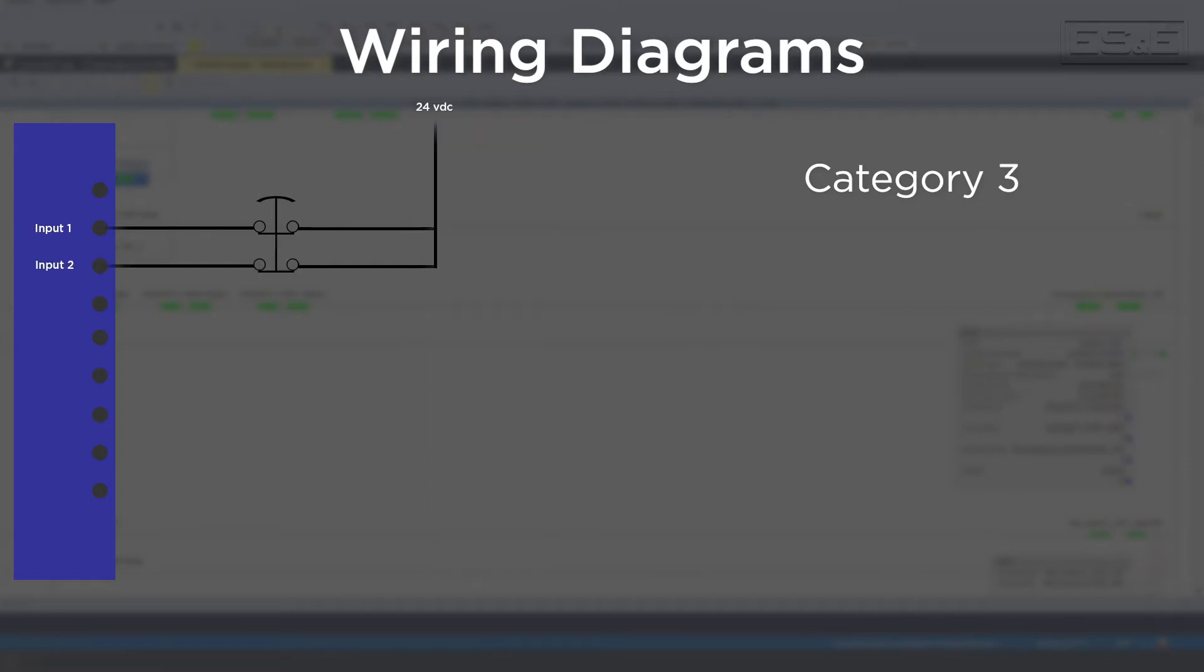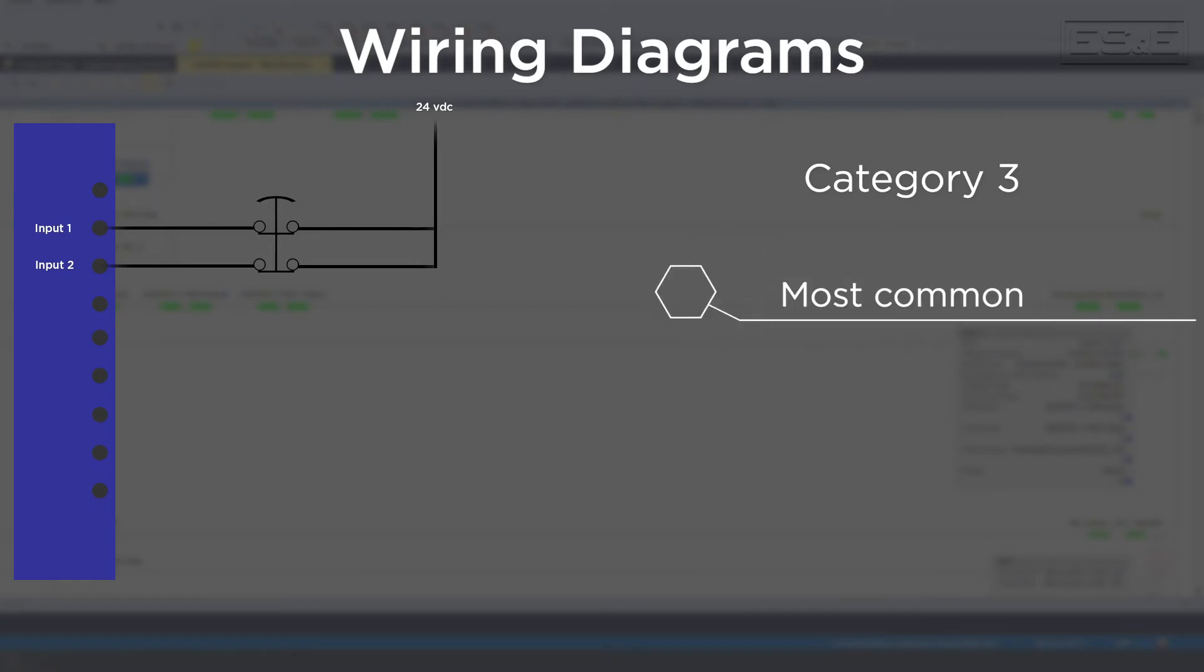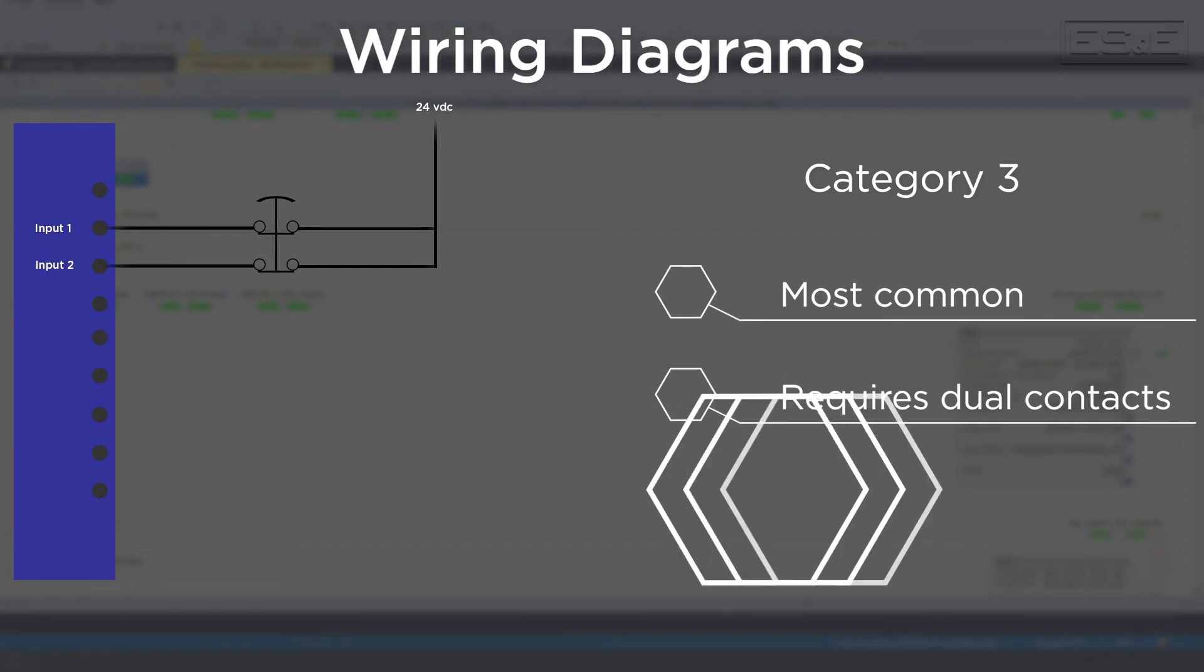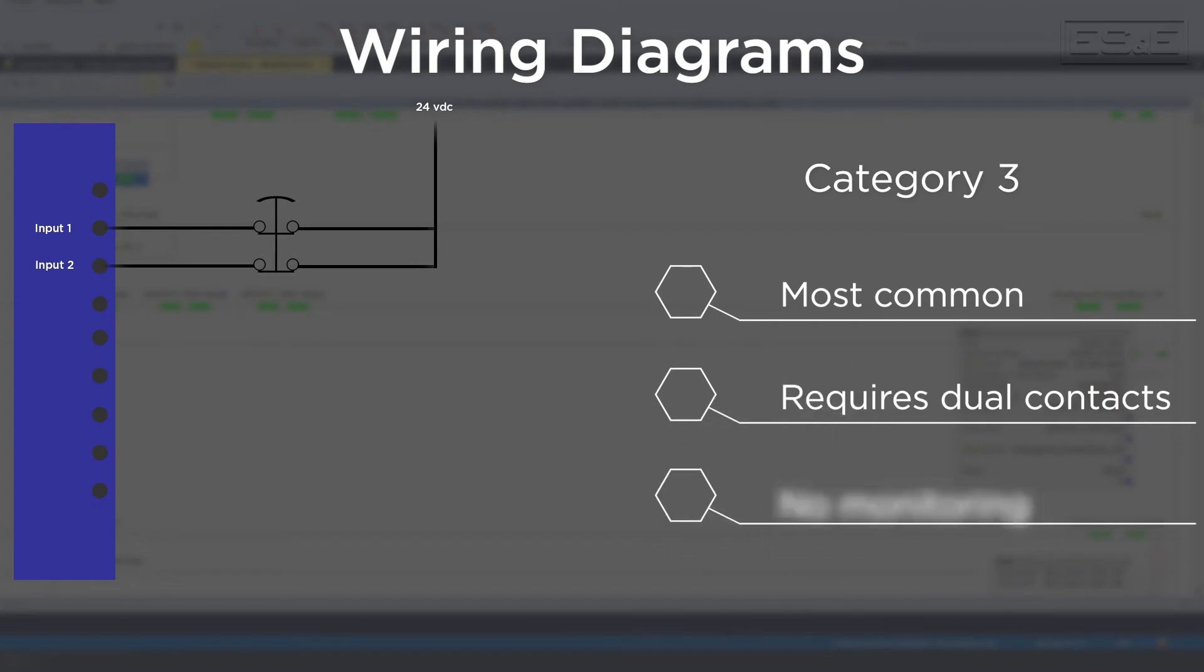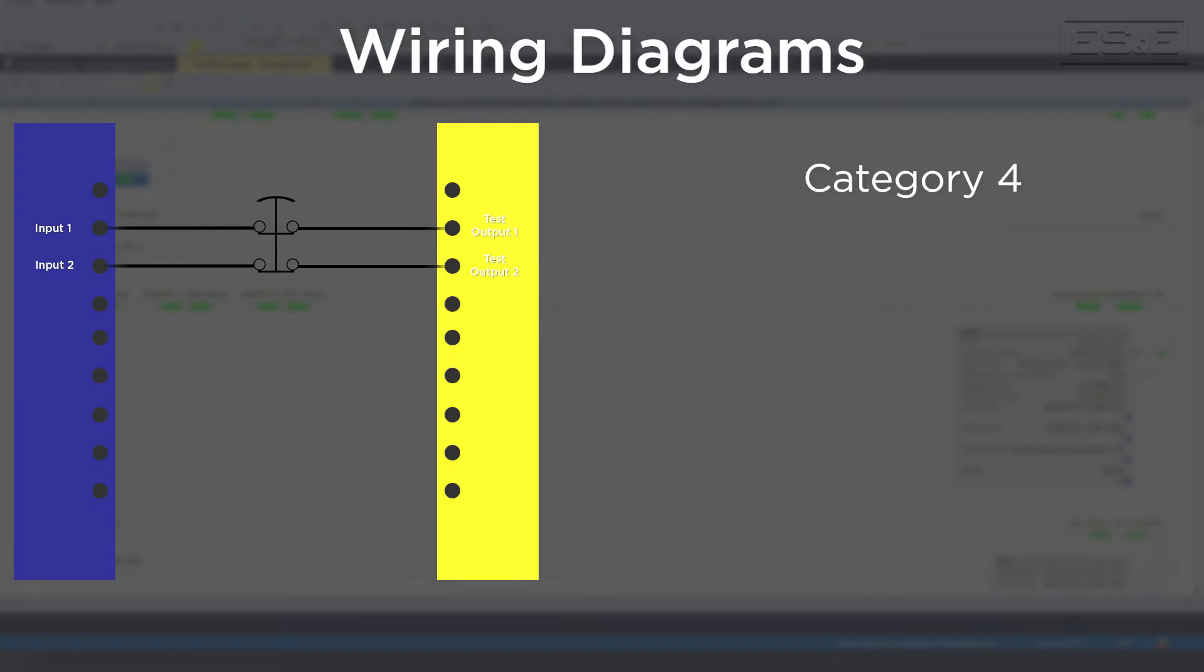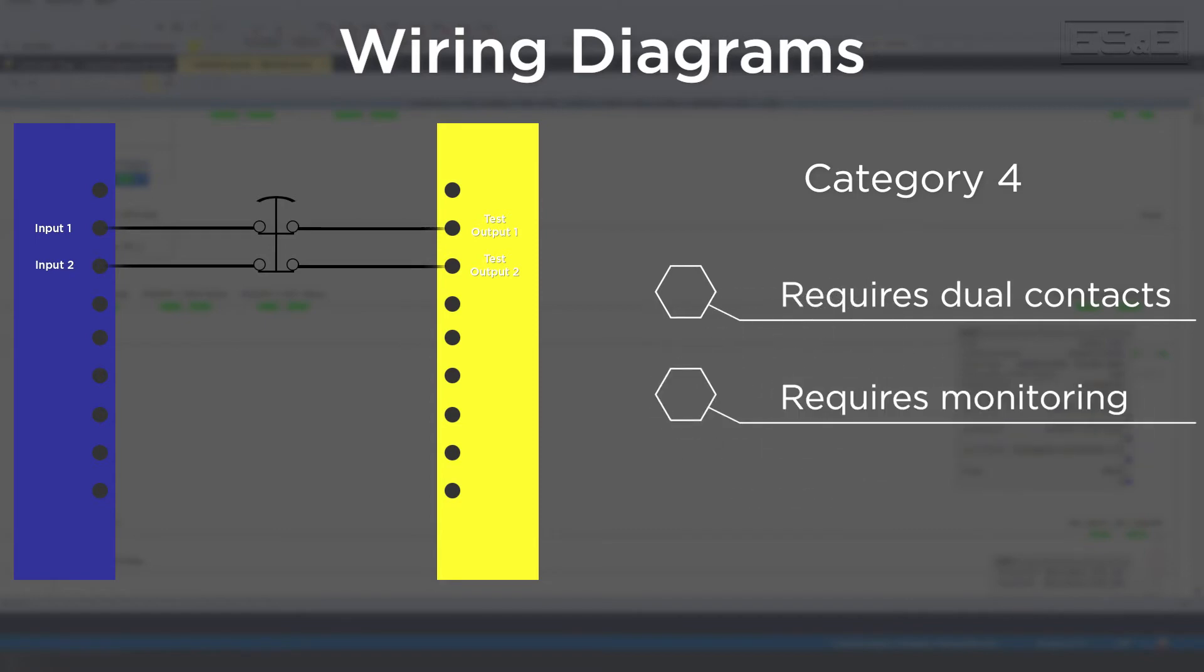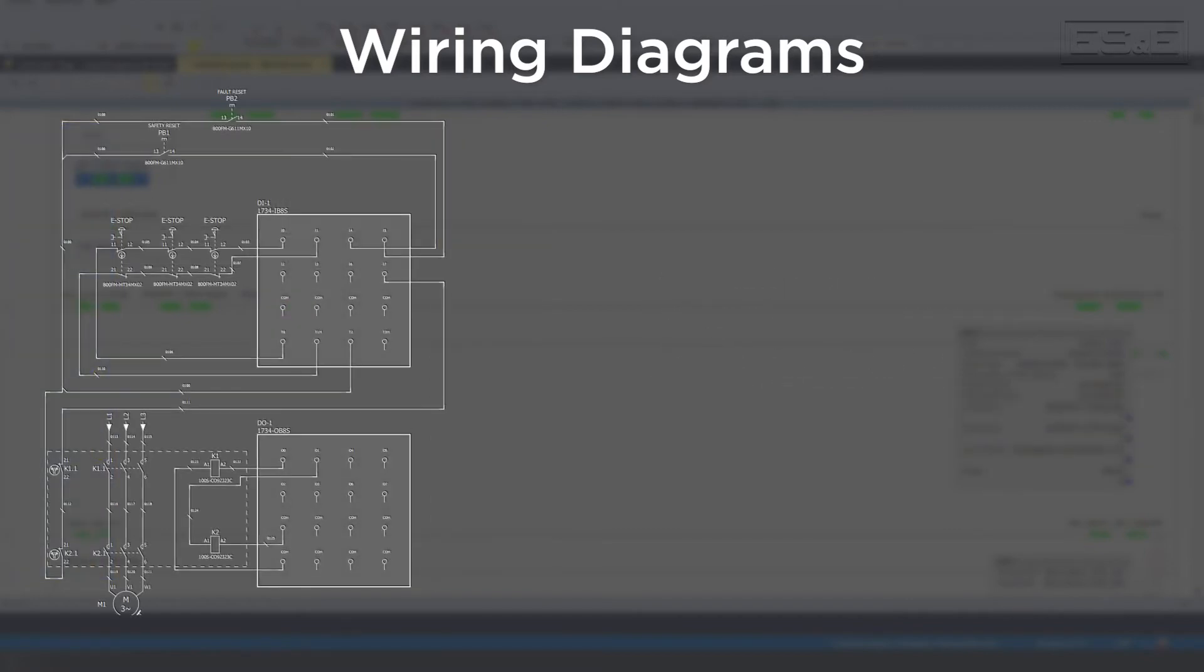Next is Cat 3, which is the most common design category. Cat 3 requires dual or redundant contacts but does not require monitoring through a test output. The third and highest category is Cat 4, which requires dual or redundant contacts as well as monitoring on both contact sets.